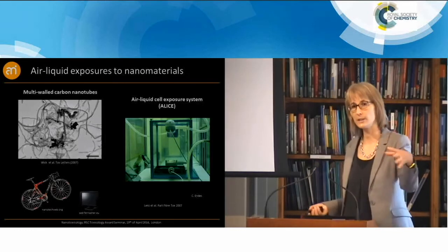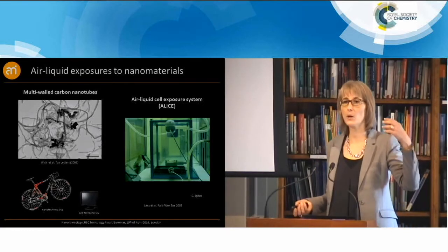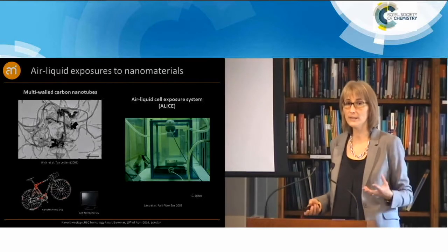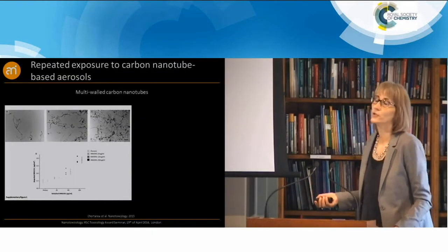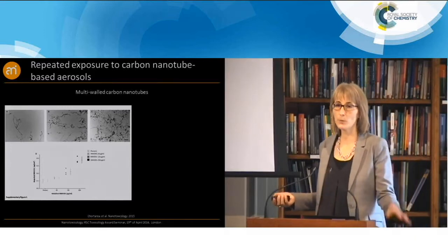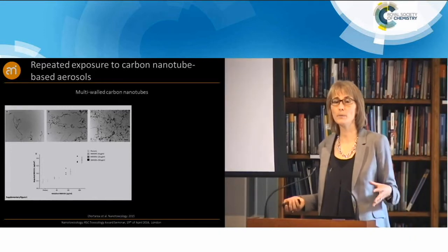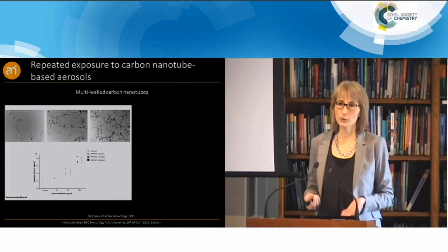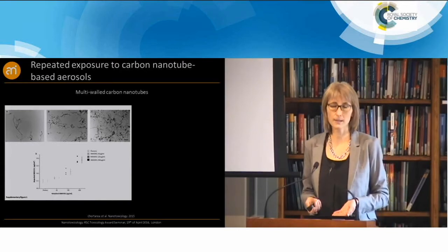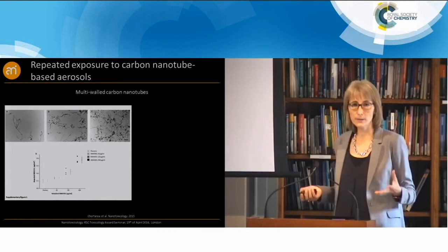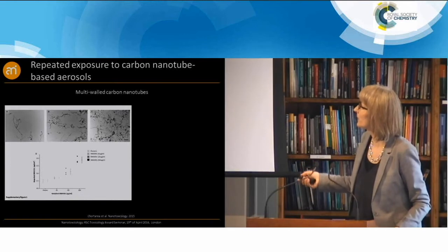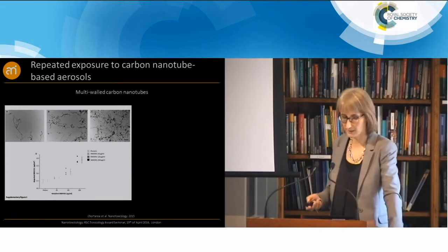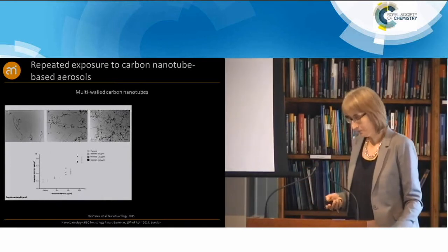So with this system we can aerosolize a well-defined nanomaterial suspension, and then the nice advantage is also that we have a quartz microbalance in the system which measures the deposited mass, so we can use different concentrations of materials resulting in different mass deposition, and we can also measure the mass with this quartz balance.